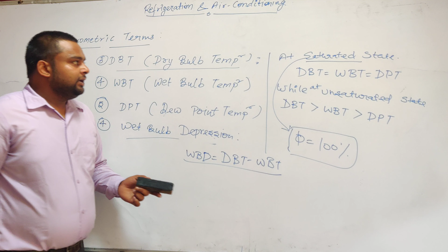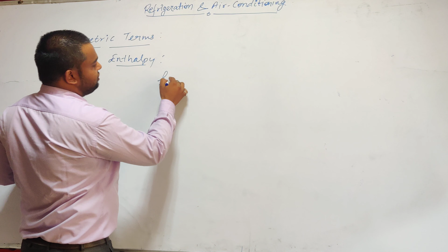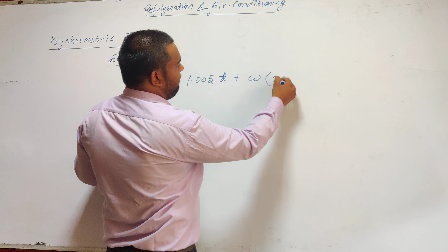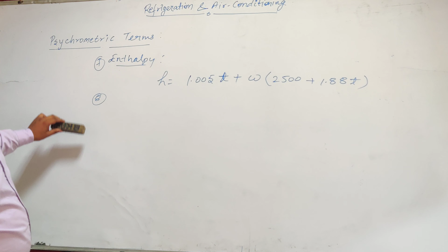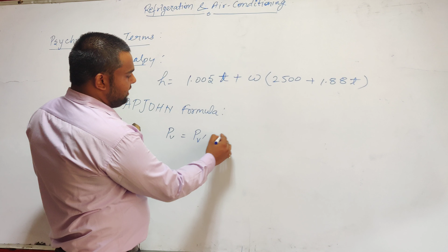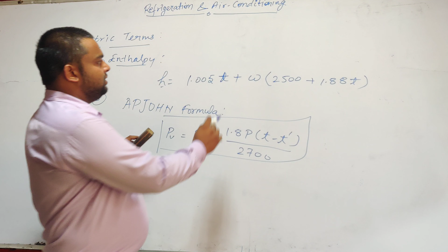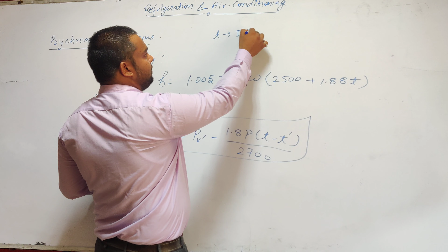Next term is enthalpy, the enthalpy of moist air. The formula used for calculation of enthalpy is H equal to 1.005 T plus omega times (2500 plus 1.88 T). This is an empirical formula used for finding the enthalpy of moist air. And last but not least, the Apjohn formula, which is used for finding the partial vapor pressure. So Pv is equal to Pv dash minus 1.8 P (T minus T dash) upon 2700. These are the empirical formulas used for finding the various properties.